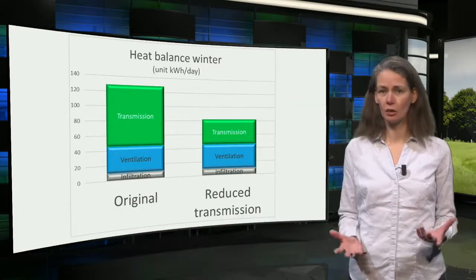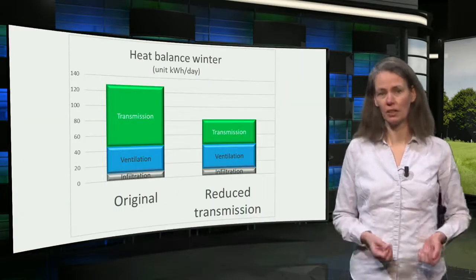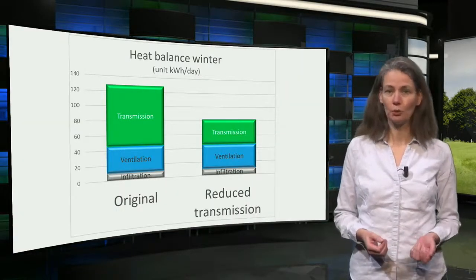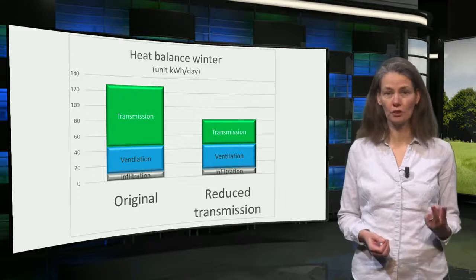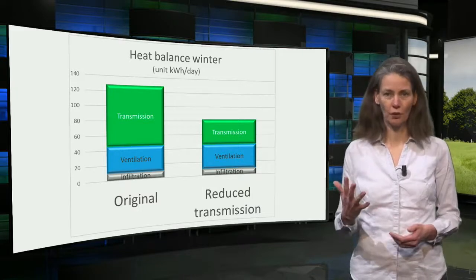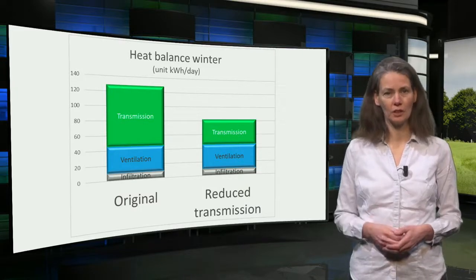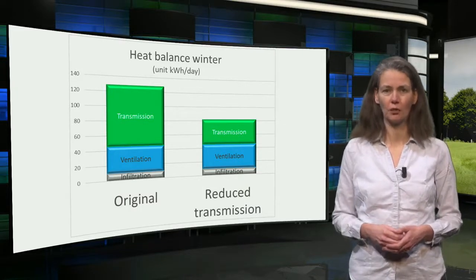There are many different ways to reduce the energy demand for ventilation. Blocking the ventilation grill, as in this image, is of course not one of them. Ventilation is a large part of the energy demand in winter. In an office room with two persons and an outside temperature of 5 degrees, this can be almost 50% of the energy demand for heating.